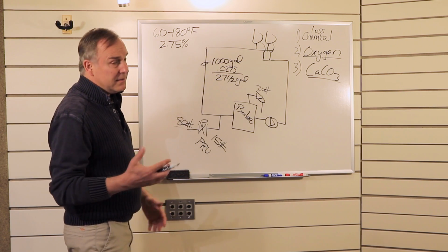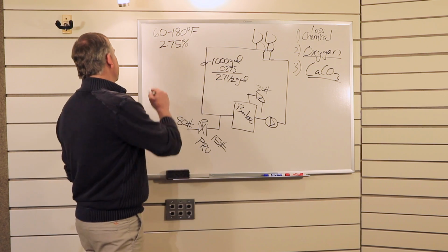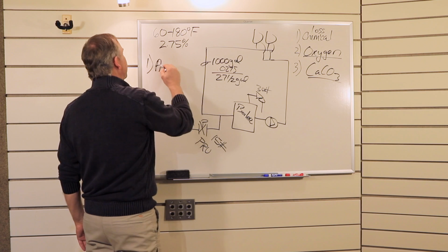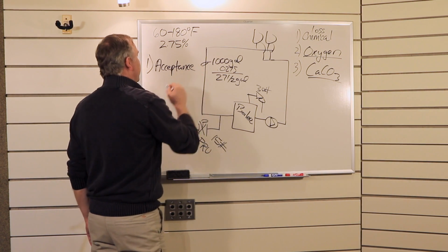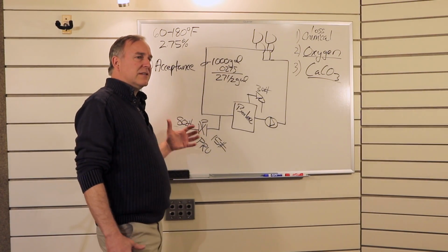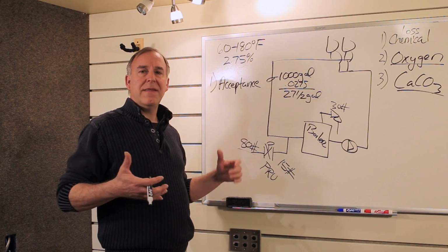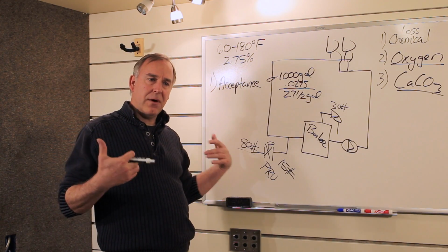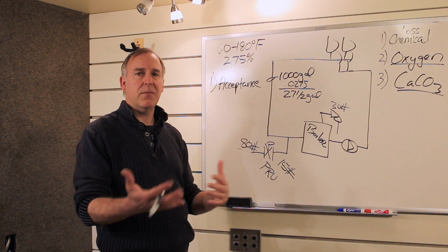All right? And this essentially is the job of an expansion tank, right? I like to say there's 2 jobs. Number 1, we have to provide what's known as an acceptance volume. Now, what does that mean? That means that we have to have somewhere for that water that's expanded to hang out while that system's hot. And then when that system cools back down, that water's there to be reintroduced back into the hydronic system. So I keep the same water in the system.